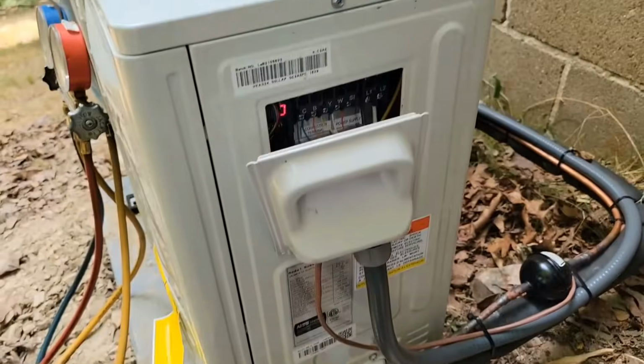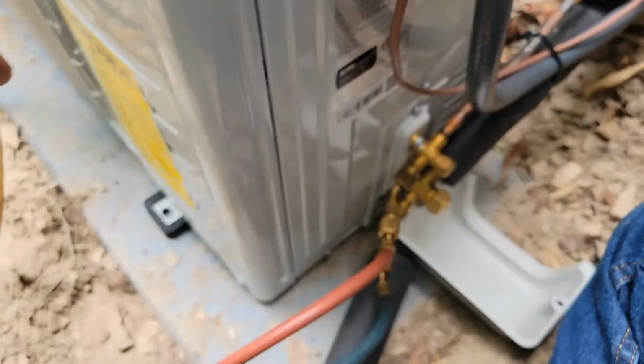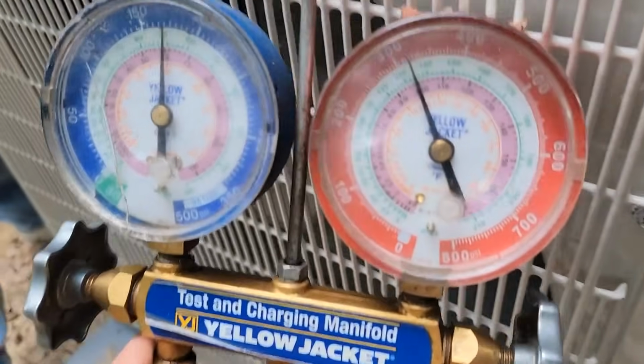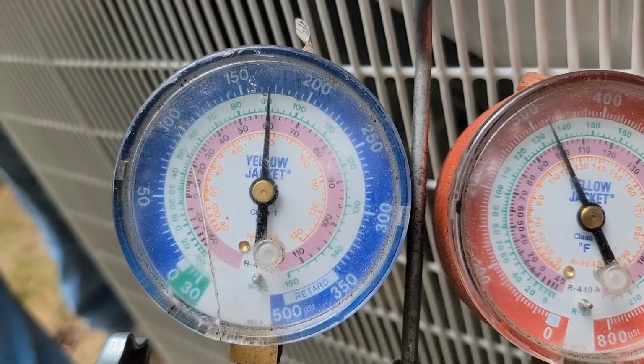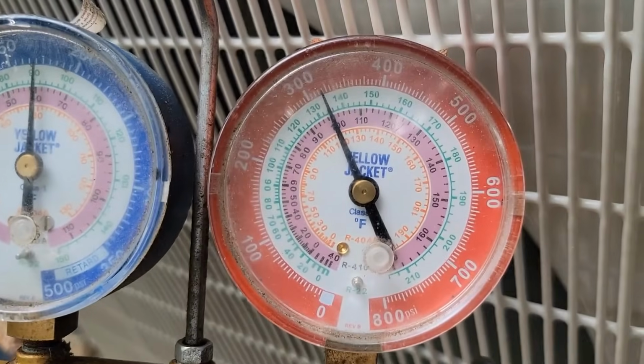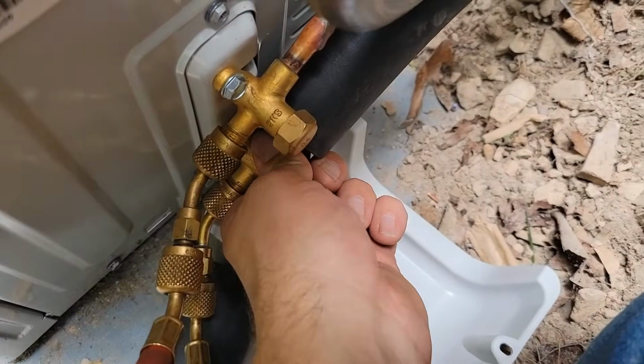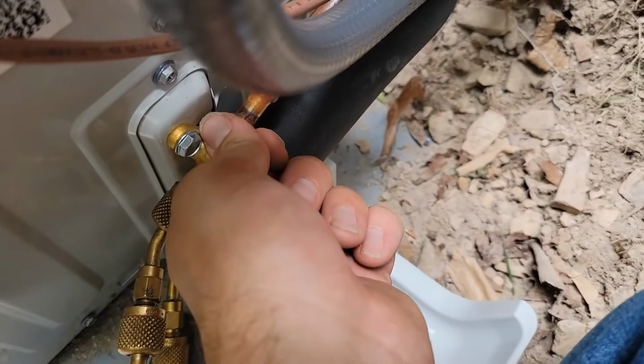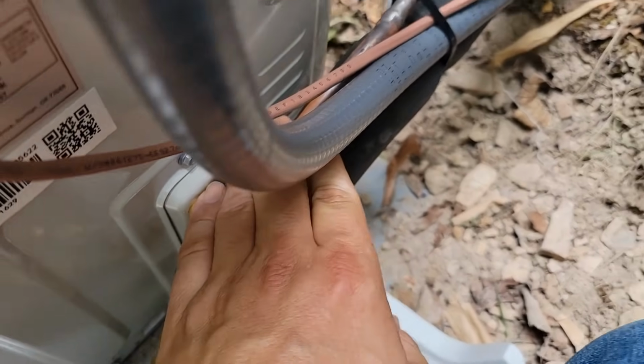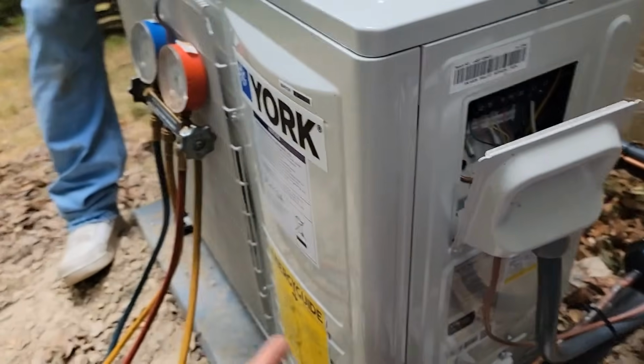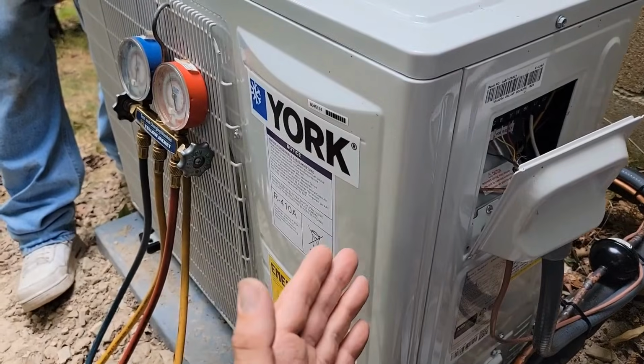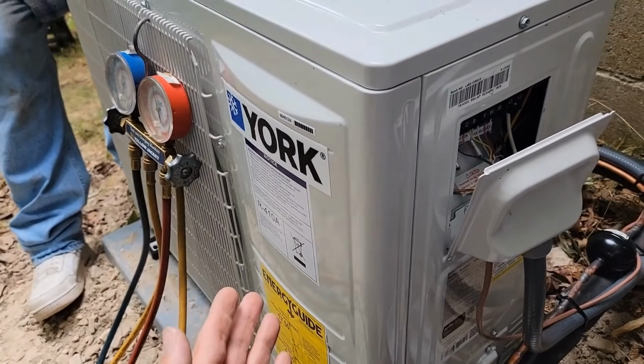Don't forget it. All right, no display on the board now. The unit's kicked back on. The pressure on the low side is about 170 and the high side is about 320. And our vapor line is nice and cool. Liquid line is warm. So now it's operating the way it should, and we're no longer energizing the reversing valve.